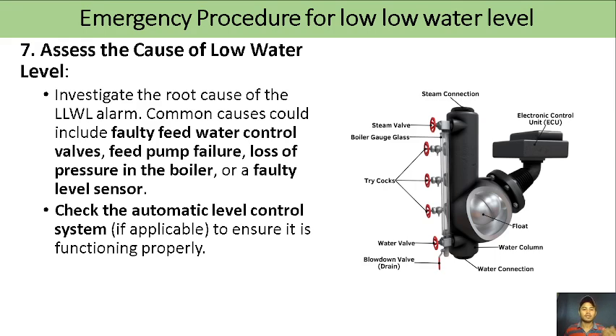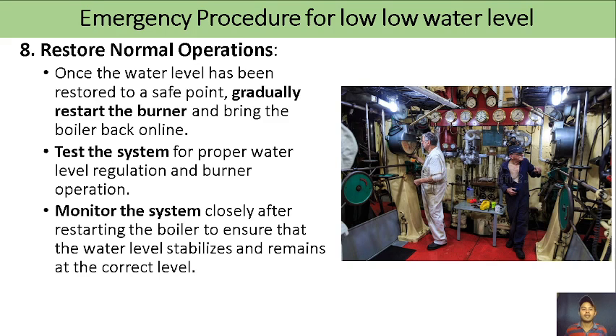So maybe it is a faulty feed water control valve, feed pump failure, loss of pressure in the boiler, a faulty level sensor. Check the automatic level control system. And then if everything is now okay, restored to normal operation, once the water level has been restored to a safe point, gradually restart the burner and bring the boiler back online. Test the system, monitor the system.